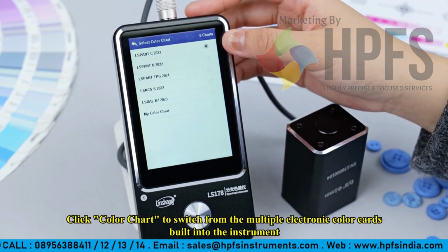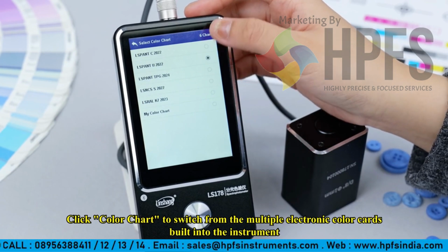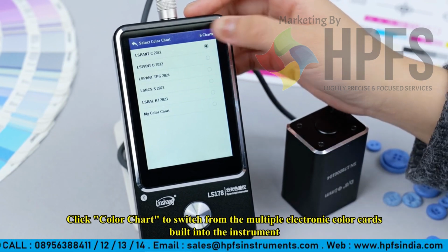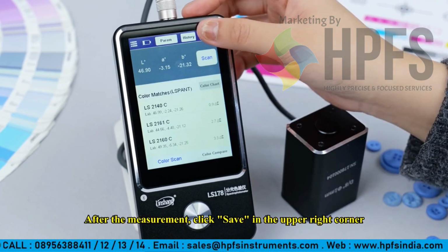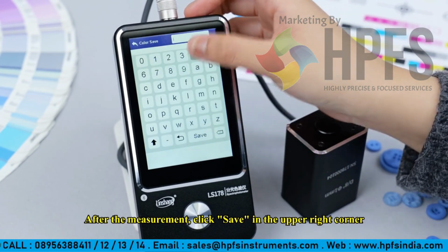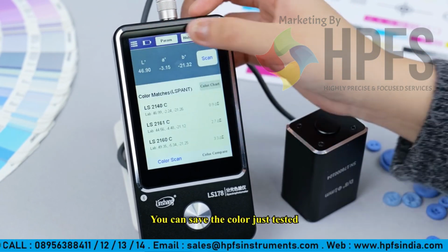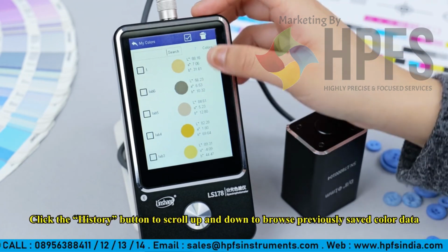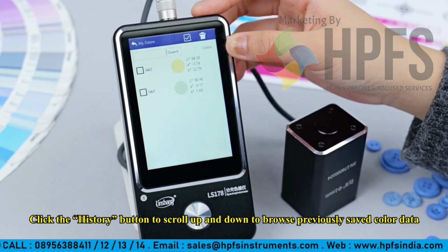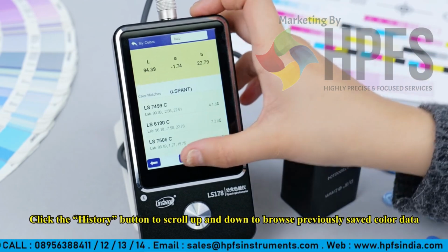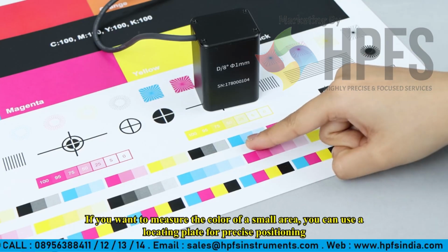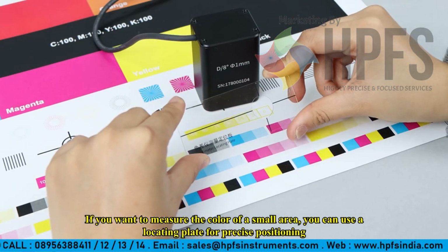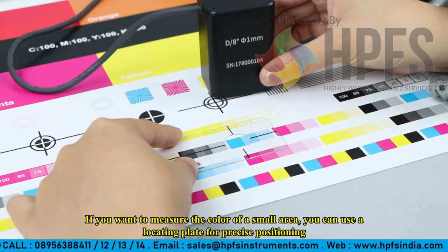Click Color Chart to switch from the multiple electronic color cards built into the instrument. After the measurement, click Save in the upper right corner. You can save the color just tested. Click the History button to scroll up and down to browse previously saved color data. If you want to measure the color of a small area, you can use a locating plate for precise positioning.